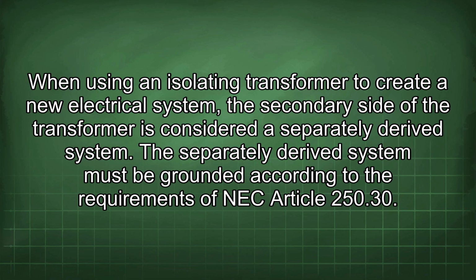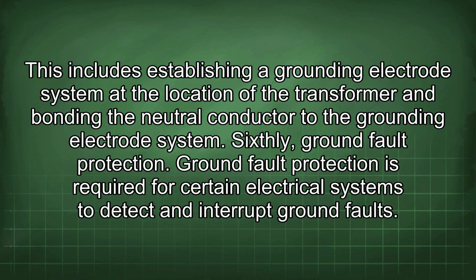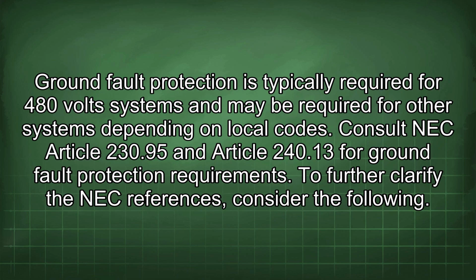The separately derived system must be grounded according to the requirements of NEC Article 250.30. This includes establishing a grounding electrode system at the location of the transformer and bonding the neutral conductor to the grounding electrode system. Sixthly, ground fault protection. Ground fault protection is required for certain electrical systems to detect and interrupt ground faults. Ground fault protection is typically required for 480 volt systems and may be required for other systems depending on local codes. Consult NEC Article 230.95 and Article 240.13 for ground fault protection requirements.